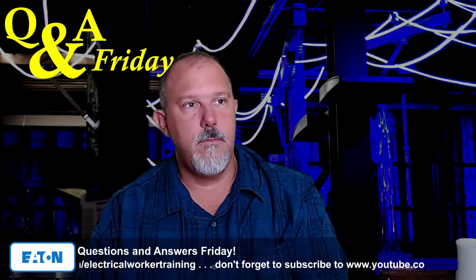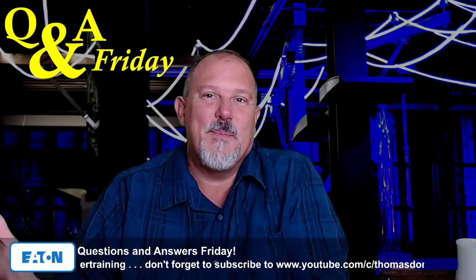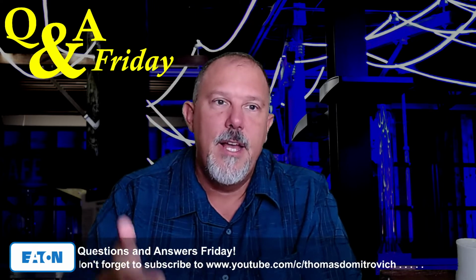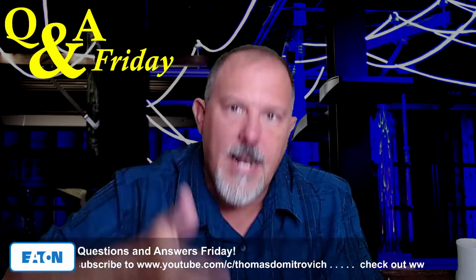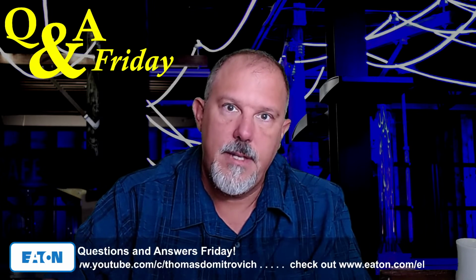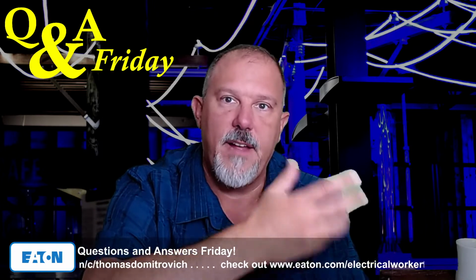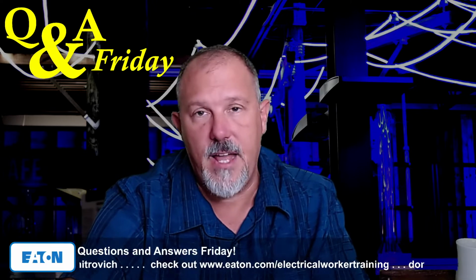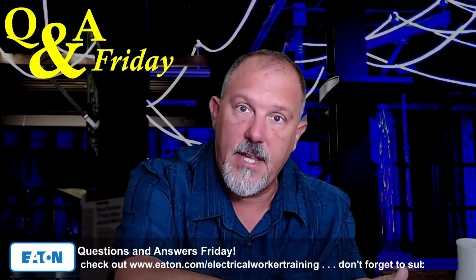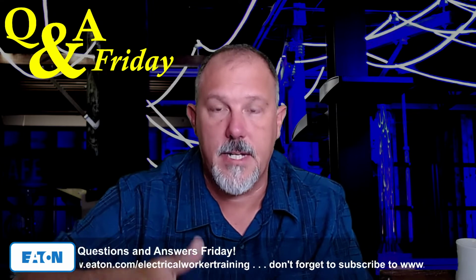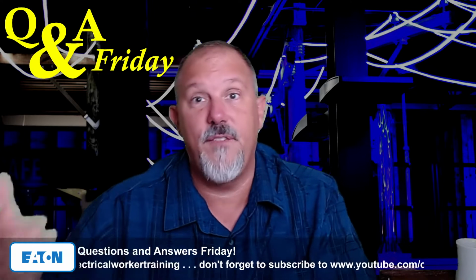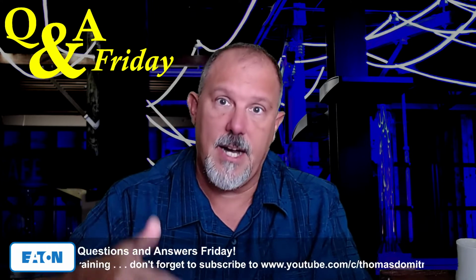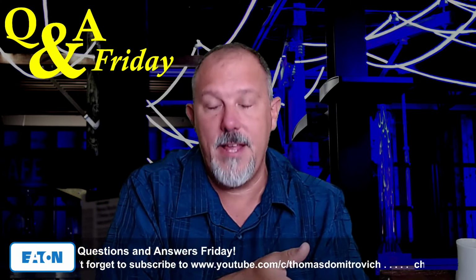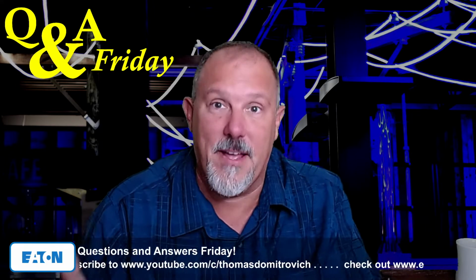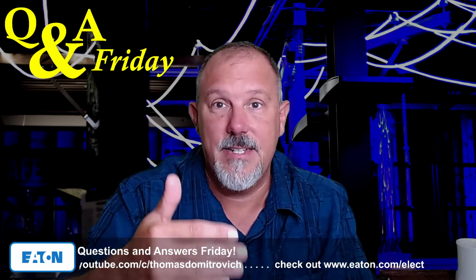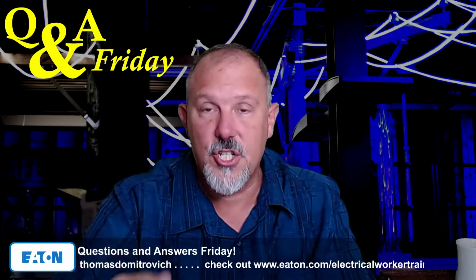But I've increased the size of my breaker, right? So I'm no longer using a 100 amp breaker at 100 amps continuous. Now I'm generating heat. My conductor is not large enough. I'd have to increase the size of the conductor by 1.25 to be able to give me the copper to take off the heat. But that's not what I'm doing. I'm not using a 100 amp breaker to protect 100 amps worth of load all the time. I'm using a 125 amp breaker to protect a 125 amp conductor, which is only carrying 100 amps. But that conductor can carry 125 amps all day long. The only reason I'm upsizing that conductor is because the breaker needs the additional copper to take the heat off.